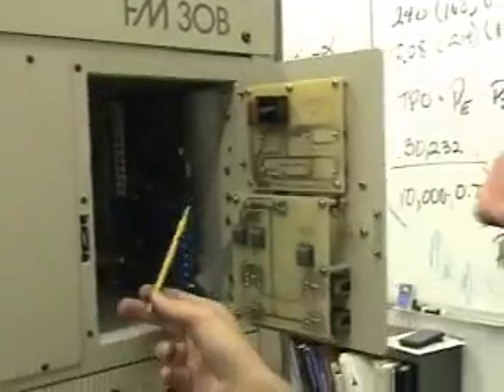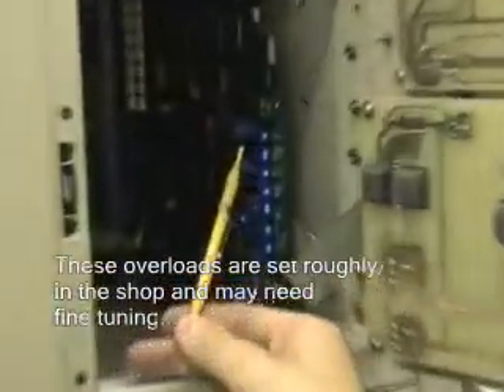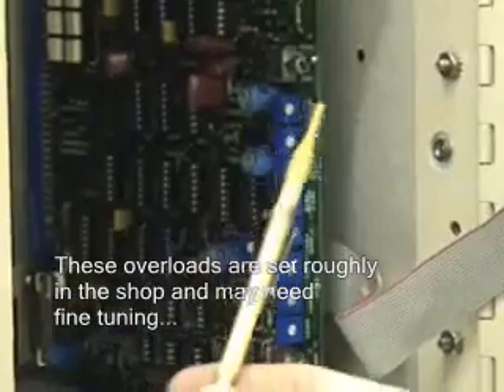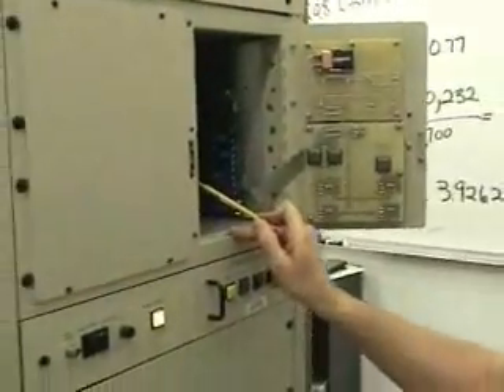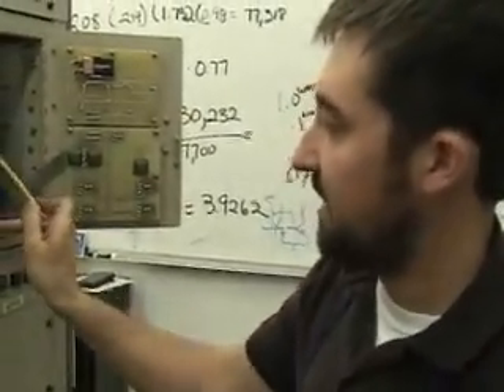All the overloads for the transmitter are on your controller card, one card for this particular transmitter in here. And you can see they're clearly labeled. You set your overloads accordingly. So you can use your manual and these pots to set whatever you want your overload to be.